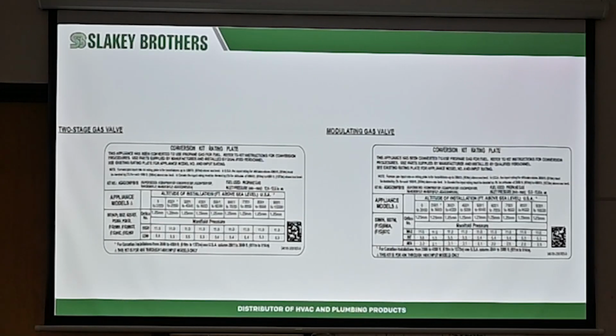Make sure you set up your gas pressure there as well. So make sure you're setting up your low and your high fire rate even there. So when you go to LP on the 987M, we're at 2,000 feet elevation. You see the high fire rate is still 11, no matter what you do. But your minimum, when you're setting up on an LP system, instead of the 0.55 is 2.2. Whereas, again, natural gas, 987. On a 2-stage, look at the difference, 5.5 and 11. So again, on natural gas and LP gas, 987M, the biggest problem is people were setting them up like a 2-stage unit. They were setting up the low fire rate at like 5.5 or 1.5, and it overheats.